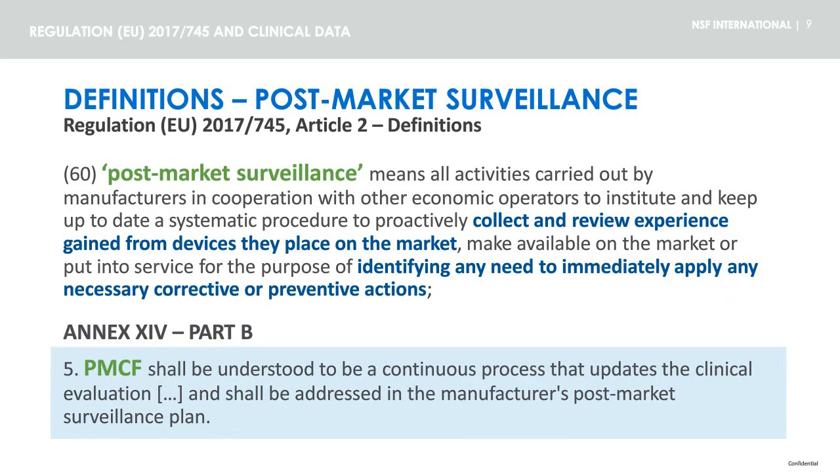To better understand the last part of the definition of clinical data, we need to go to the definition of post-market surveillance, PMS. Manufacturers are required to implement a post-market surveillance system to collect and review experience data from devices placed on the market, so that they can immediately apply any necessary corrective or preventive actions. A PMS system should also include post-market clinical follow-up activities, PMCF, which is a continuous process to proactively collect clinical data. We will discuss methods for gathering PMCF data later in this presentation.